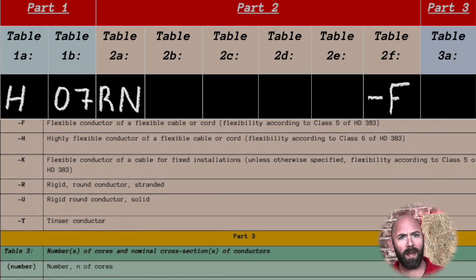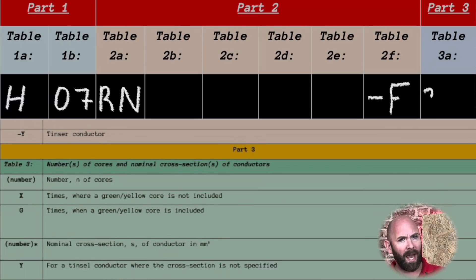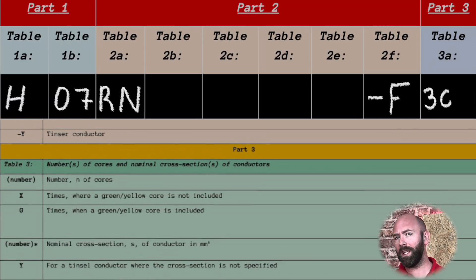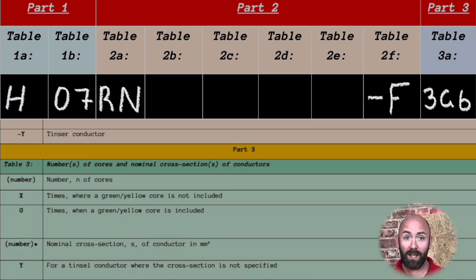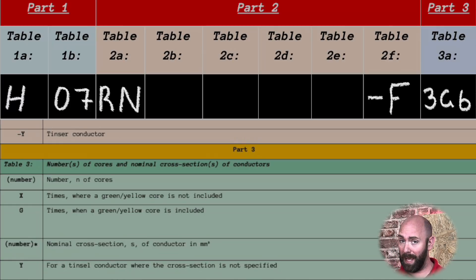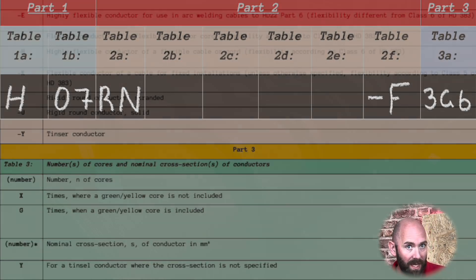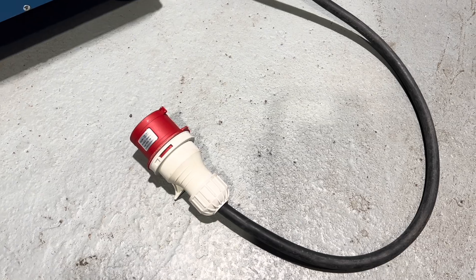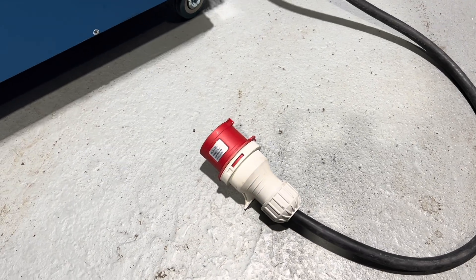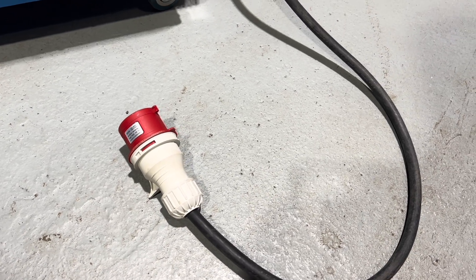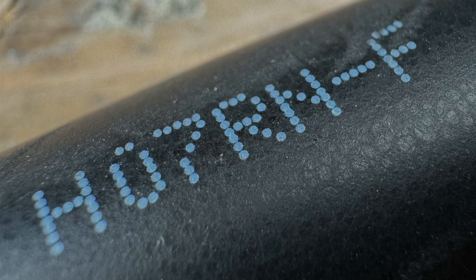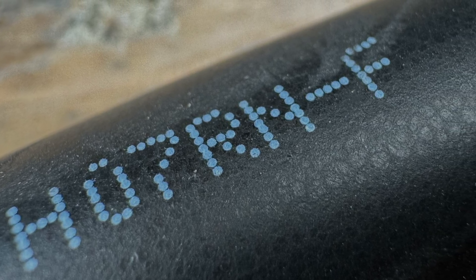The last part of this cable is the size and number of cores. Our cable is 3G6, meaning it's a 3-core 6mm cable, and the G tells us it's a green and yellow conductor included in the cable — what we normally use as our protective conductor. And this is the cable: a tough heavy-duty flexible cable which will have applications in marine locations or at festivals for supplying power from generators.